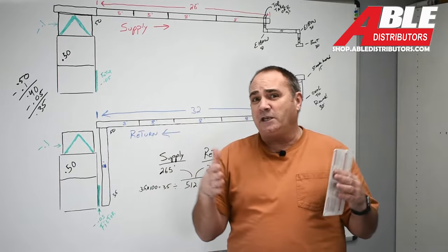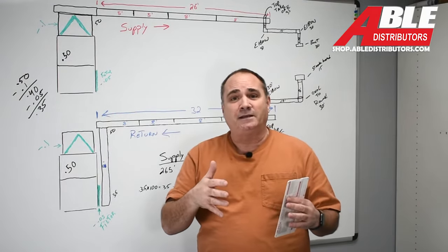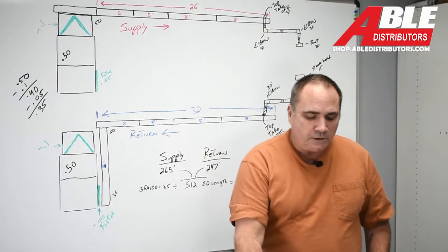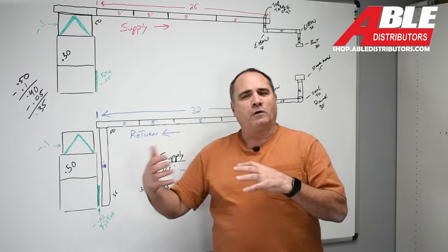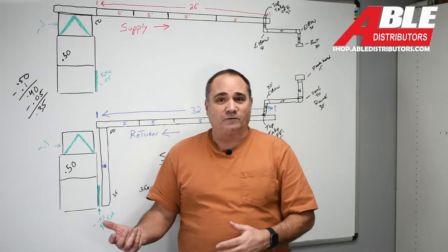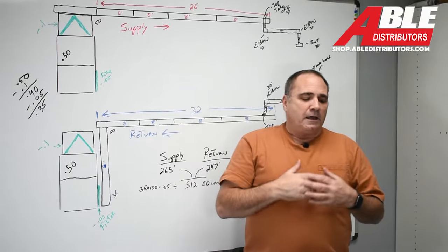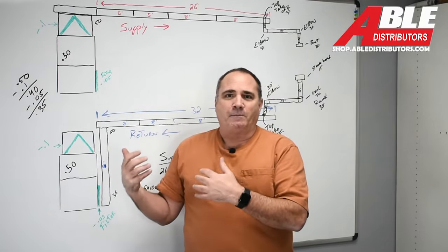Any single time we change direction or we reduce the size, we have equivalent length that we add up. Now we're used to using those terms, equivalent length, when we're venting a 90% furnace. Every elbow is 5 feet or 10 feet or whatever it is. This is the same type of thing.